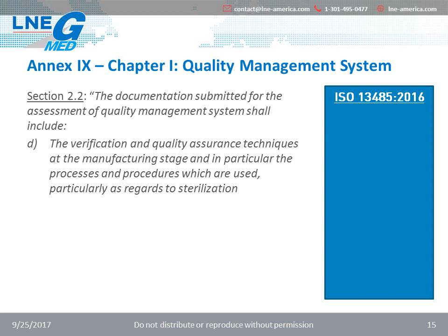Another element to provide is the documentation related to verification and quality assurance techniques, processes, and procedures at the manufacturing stage, with the emphasis on the sterilization process. Those are requirements that you can also find in the ISO in sections 7.5 and 8.2.6. Section 7.5 is related to production and service provision and covers all aspects of product manufacturing and validation, but also has some particular requirements for sterile products. One, for example, is the maintenance of records of sterilization process parameters for each sterilization batch. The second, 8.2.6, is a section related to monitoring of product and calls for documented procedures to verify that the product requirements have been met. So in both cases, you would have to have the procedures in place to answer what the regulation wants, but also what you can find in the ISO.